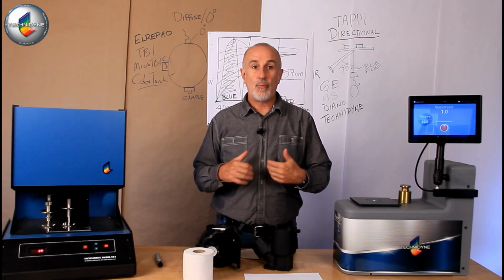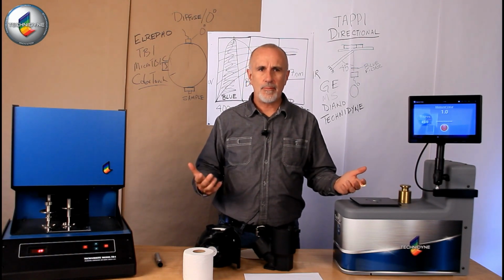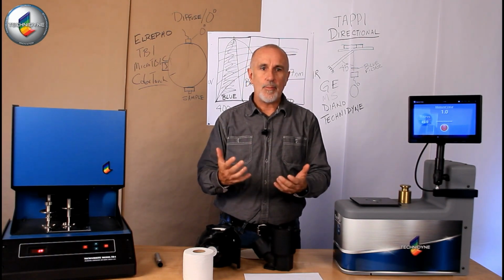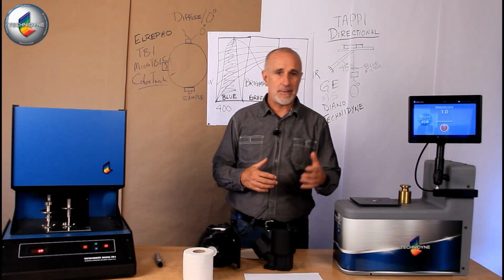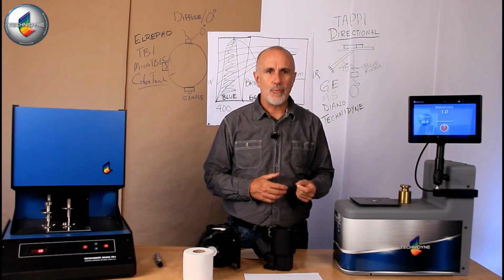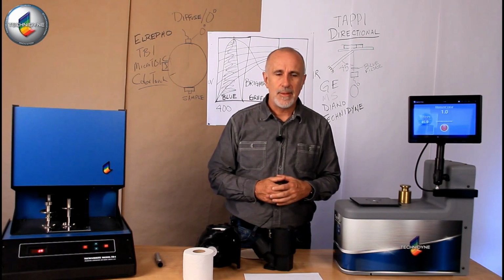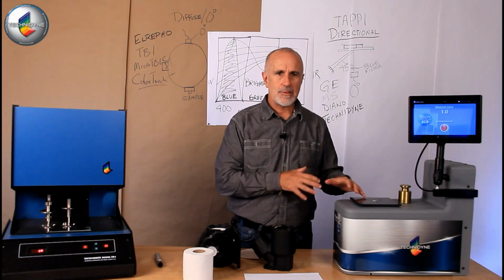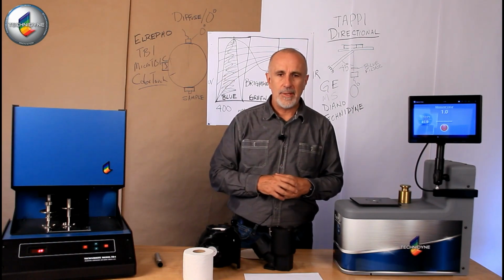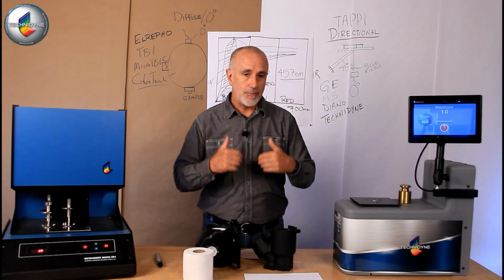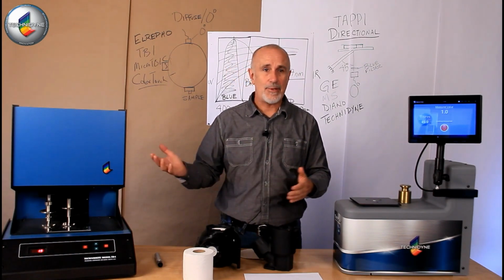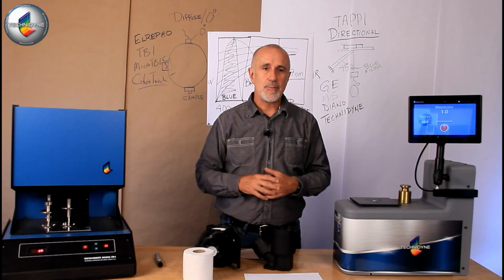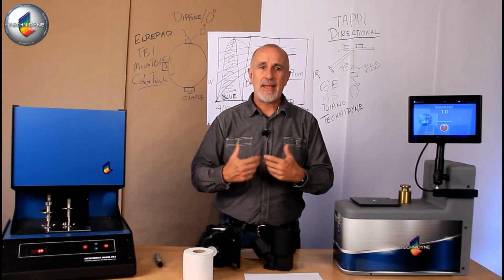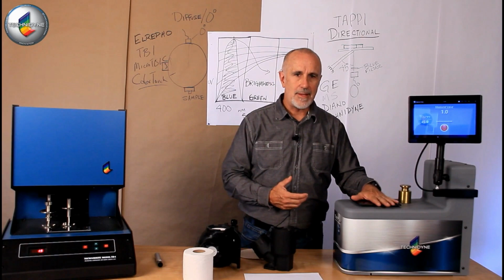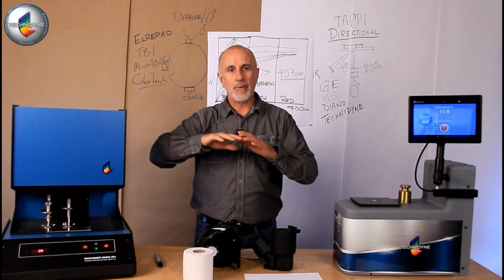So we've defined what brightness is, and the methods we use for making the brightness measurements. As a company, every instrument we manufacture meets a specific paper industry standard, whether it's a TAPPI or ISO method. And so we put a lot of time, effort, and research into that. You make a big investment to purchase one of those pieces of equipment. So if you've gone through the purchasing process and the justification of why you need a TAPPI or ISO instrument, the important thing is to keep that instrument maintained and calibrated properly so that it generates a TAPPI number or an ISO number over time.